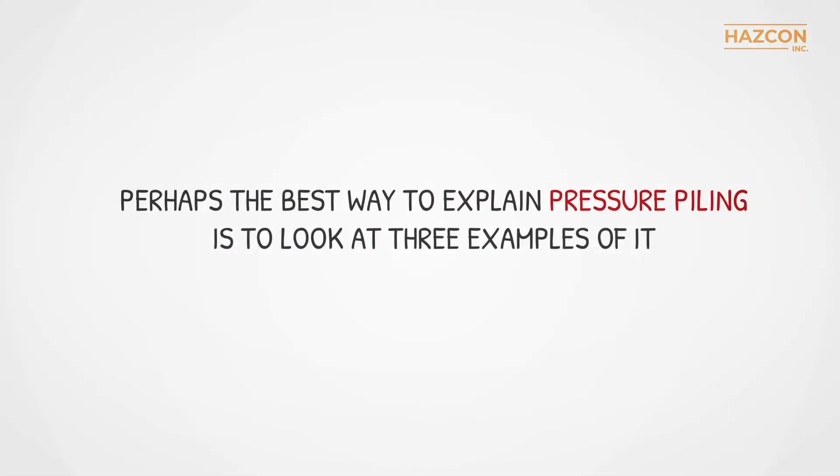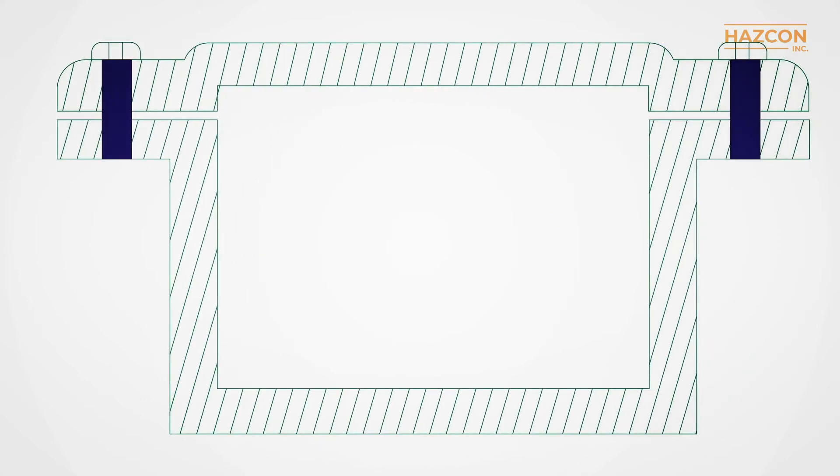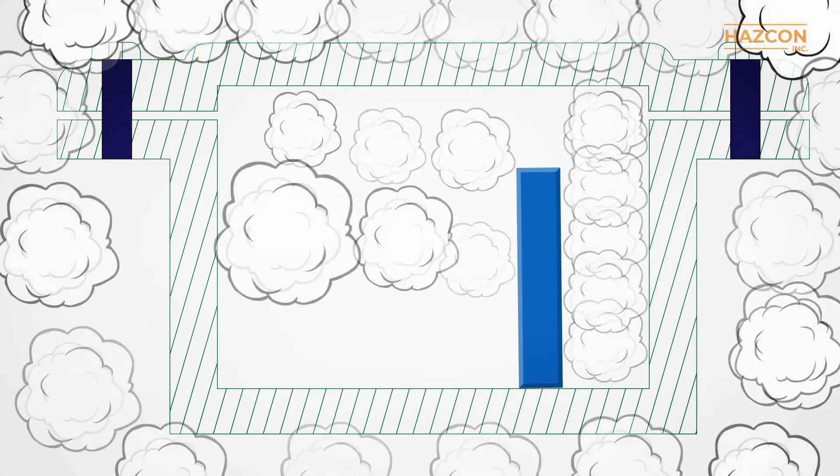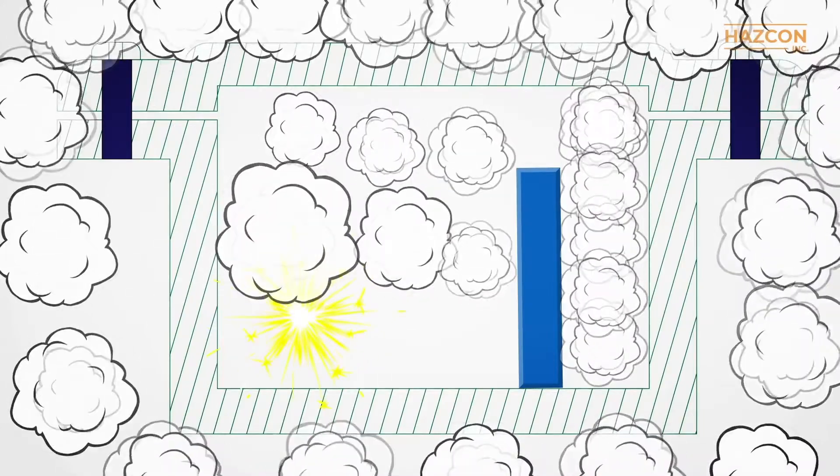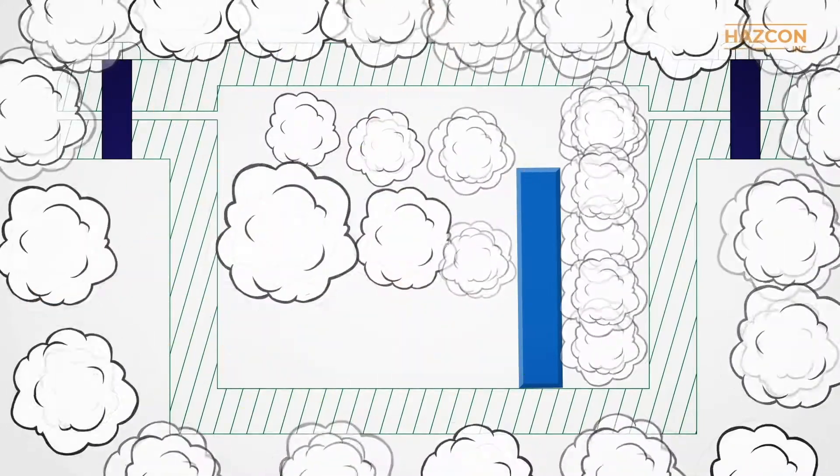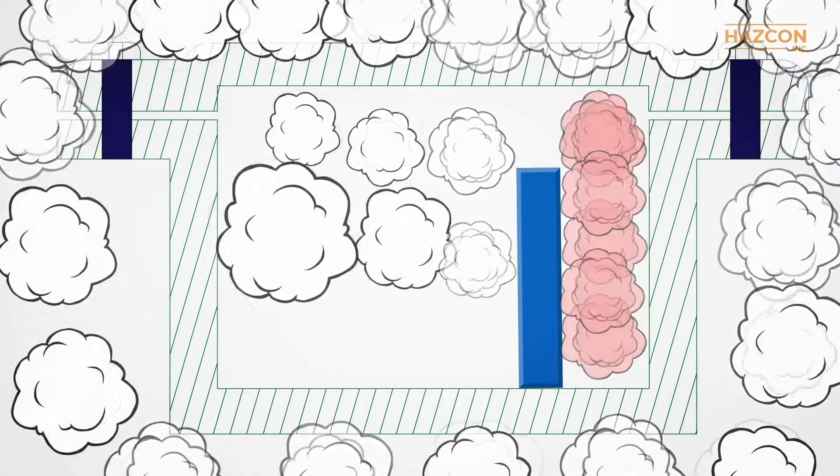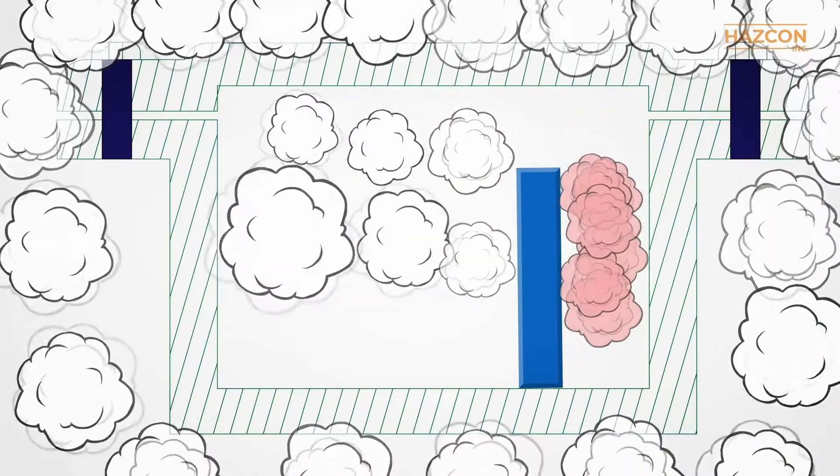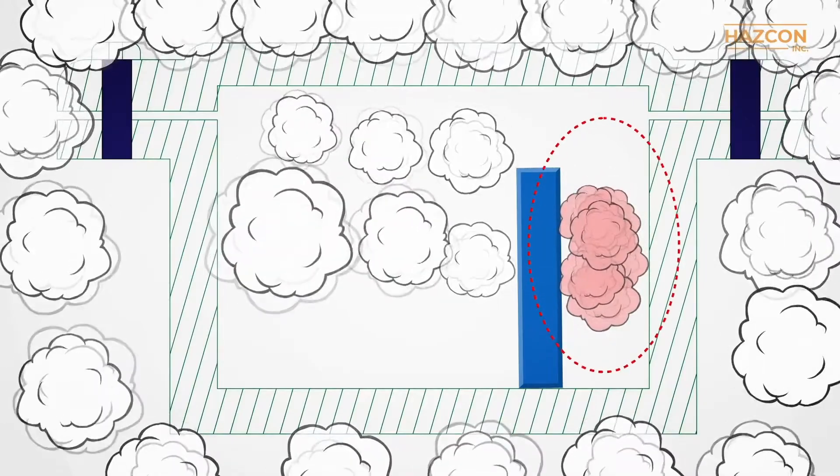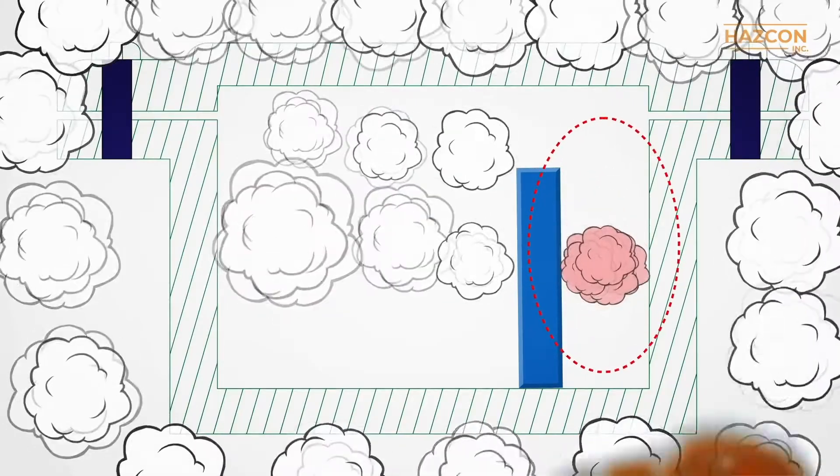Perhaps the best way to explain pressure piling is to look at three examples of it. In our first example, the design of an explosion-proof enclosure with two or more compartments allows unburned gas to collect in a particular space within the enclosure. The unburned gas in this space becomes compressed and therefore highly pressurized before being ignited. This pressure piling effect will lead to a higher explosion pressure.